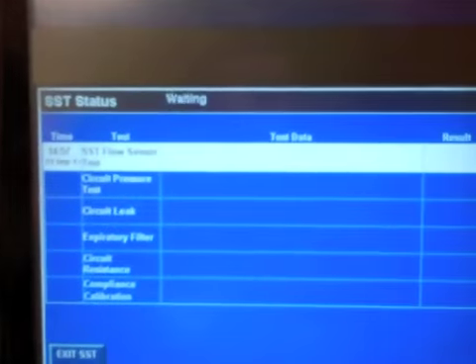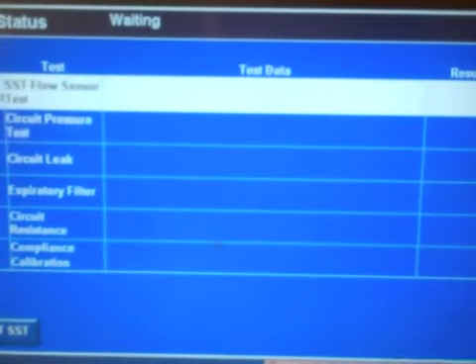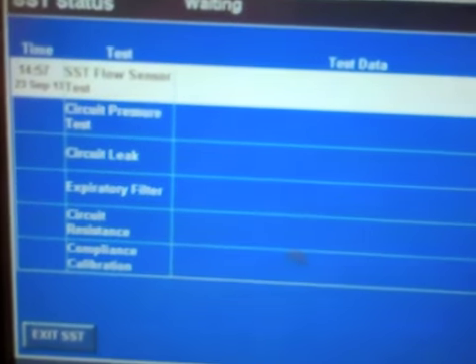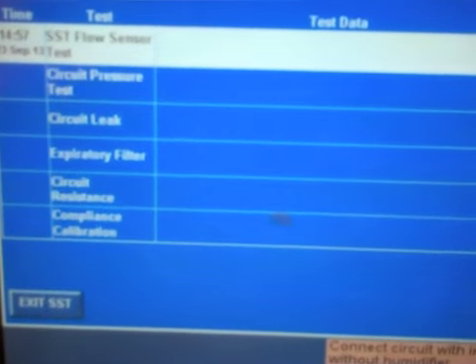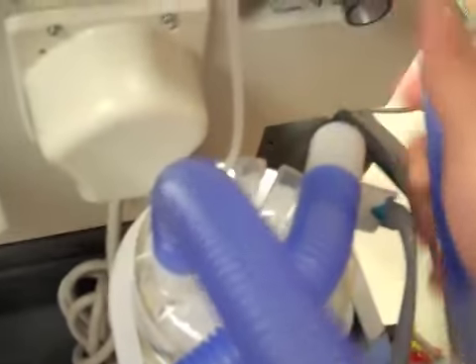This is the screen that will be running our SST. You can see we're going to do our flow sensor, circuit pressure, circuit leak, expiratory filter, circuit resistance, and compliance. Down in this bottom right corner is where we're going to get our prompts. Right now it's saying connect our circuit with inspiratory filter and without the humidifier. So what I typically do is pop this off, get off my humidifier, and just pop that on. So I bypassed my humidifier.